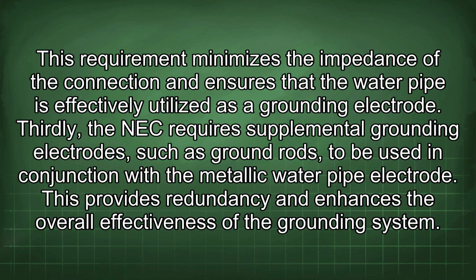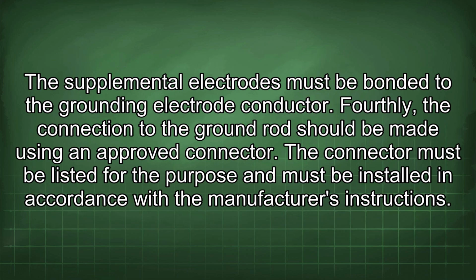This requirement minimizes the impedance of the connection and ensures that the water pipe is effectively utilized as a grounding electrode. Thirdly, the NEC requires supplemental grounding electrodes, such as ground rods, to be used in conjunction with the metallic water pipe electrode. This provides redundancy and enhances the overall effectiveness of the grounding system. The supplemental electrodes must be bonded to the grounding electrode conductor.